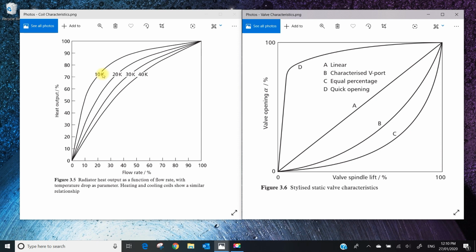And this results in control valves starting to hunt. And what normally happens is, because we don't know this is actually happening, you can't see this, we just see we have hunting control valves. So what do we do? We start to widen the proportional band, try to slow down that hunting, and we widen it and widen. I'm sure a lot of us have done a lot of commissioning. There have been times when you're just sitting there for hours and you widen the proportional band, you just can't get the control loop to stabilize. And it's because you've got the wrong size valve in there. So we tend to end up, whether we realize it or not, using software to try and resolve hardware design issues.